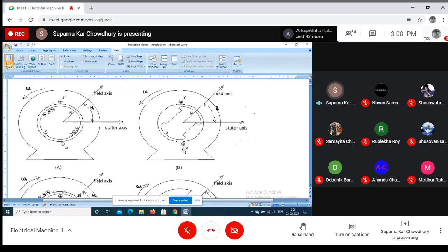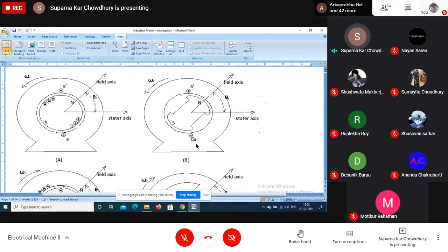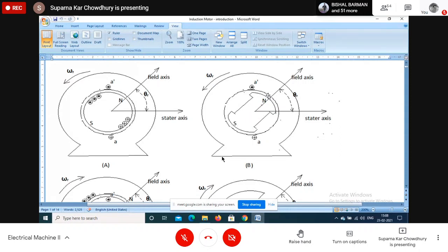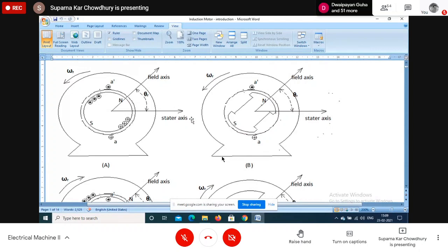In the second configuration, we again have the armature on the stator and field on the rotor, but the field is no longer cylindrical. This type of construction is called salient pole construction, where there are projected poles and a concentric winding on the structure which creates north and south poles. So here the armature is on the stator and field is on the rotor, but the field is salient pole in nature.